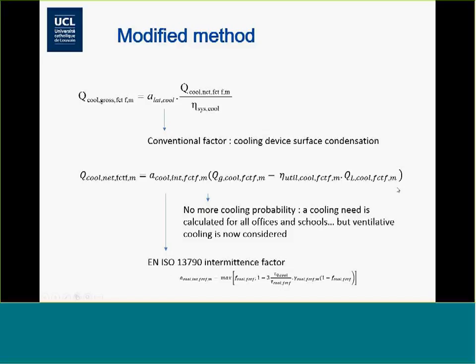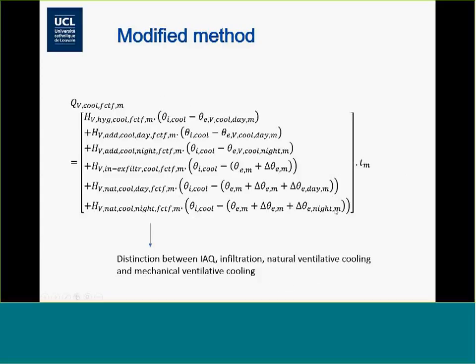And the biggest point that will change is the calculation of losses, and especially ventilative losses. We now have a distinction between various terms: one for hygienic air quality ventilation, one for infiltration and exfiltration, so uncontrolled ventilation, two for additional mechanical ventilation, one day and one night, and two for natural intensive ventilation, day and night. So we now have a quite comprehensive framework for all kinds of ventilation that can be set in the building, either natural or mechanical, and either day or night, or continuous, such as infiltration.